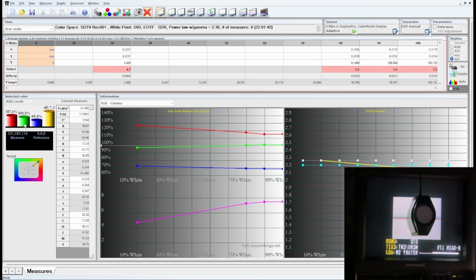On a few Sony consumer sets and on Ikegami brand PVMs, they actually use red as the reference level, and you'll see that in the settings or the service manual of those. So you'll have to be careful, but 95% of the time, green is your reference level. That means I am never going to touch green. Now on this set here, it doesn't even let me touch green, but on the Sony PVM right below it, it does let me touch green, but I just shouldn't ever touch it.